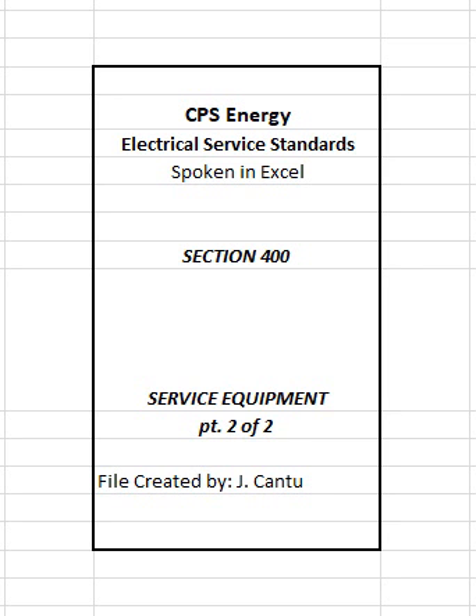The meter disconnect switch shall be labeled permanently as meter disconnect and not be utilized as a switching device for customer loads or take the place of customer's service disconnecting means required by the NEC and applicable codes on the load side of the meter socket. 408.1 Meter disconnect rating. The meter disconnect switch nominally rated not in excess of 600 volts shall be non-fused for installations with available short circuit current ratings of 10,000 amps or less and be listed as suitable for service equipment.